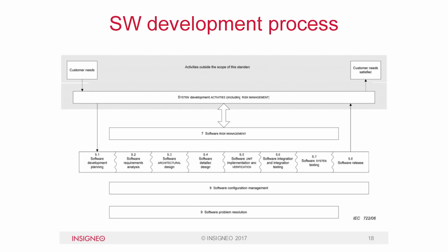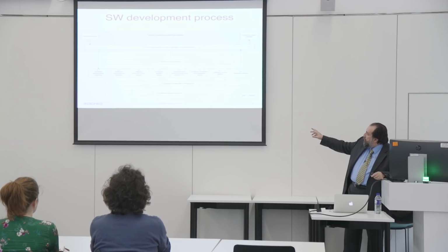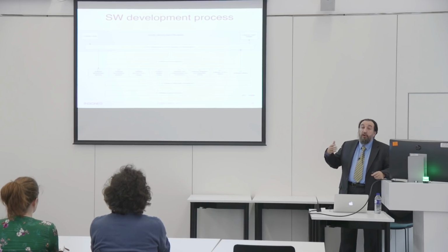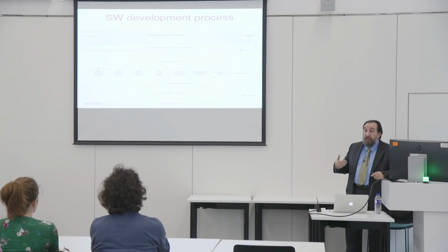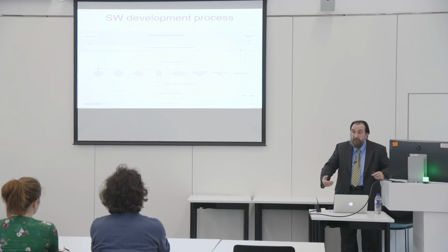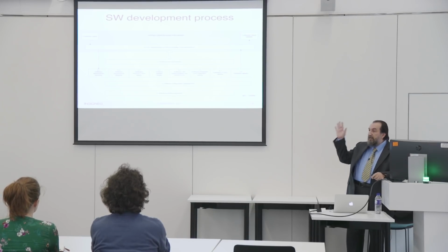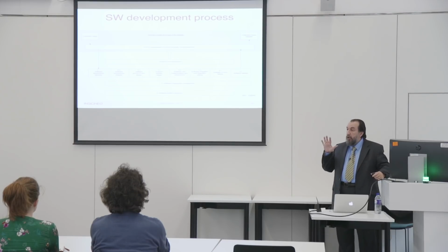There are two important elements in this standard. The first is that the standard regulates the entire life cycle, from the very early software development planning when you set the specification of what the software should do, to the very end: the software release, the configuration management, and the post-marketing monitoring when bug reporting comes in and you have to fix and update. The entire life cycle has to be controlled.